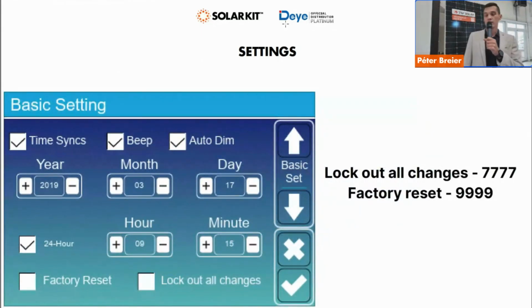So first of all, you get into the first page of the basic settings, and here you have two very important and one mildly important part. Basically, you want to remove the check mark from Beep, because if you don't do that, the inverter will continuously make a very annoying sound. Other than that, you have the lockout all changes option here. You want to remove the check mark from that. If you don't remove the check, it's basically there. It automatically gets there after a period of time. If you don't remove that, you will not be able to change any settings on the inverter. You will be able to see them, but you will not be able to change them. If you remove that mark, then you save it with the bottom right icon.